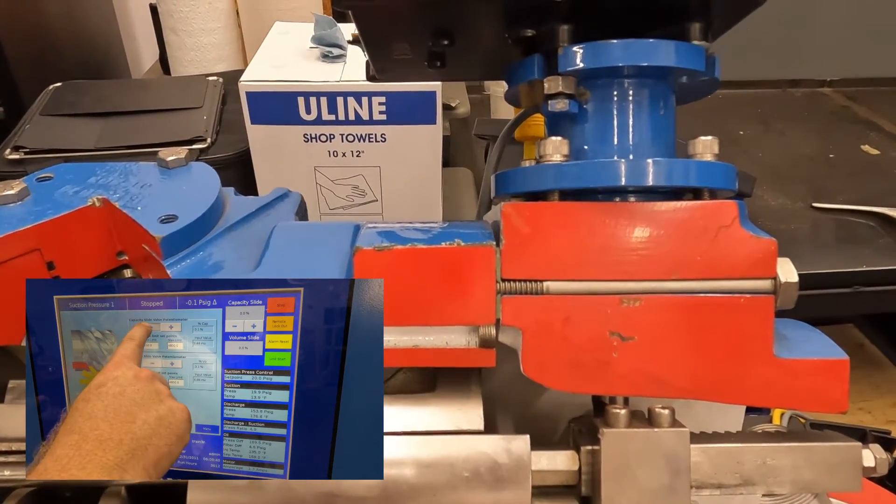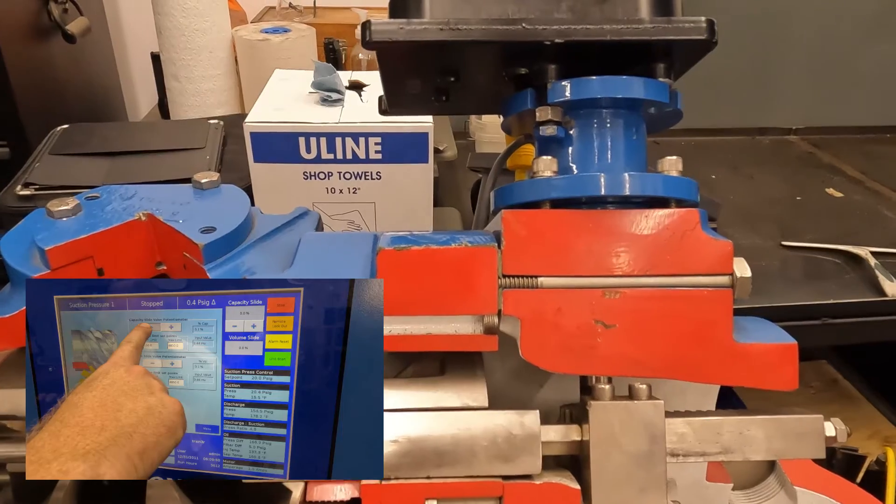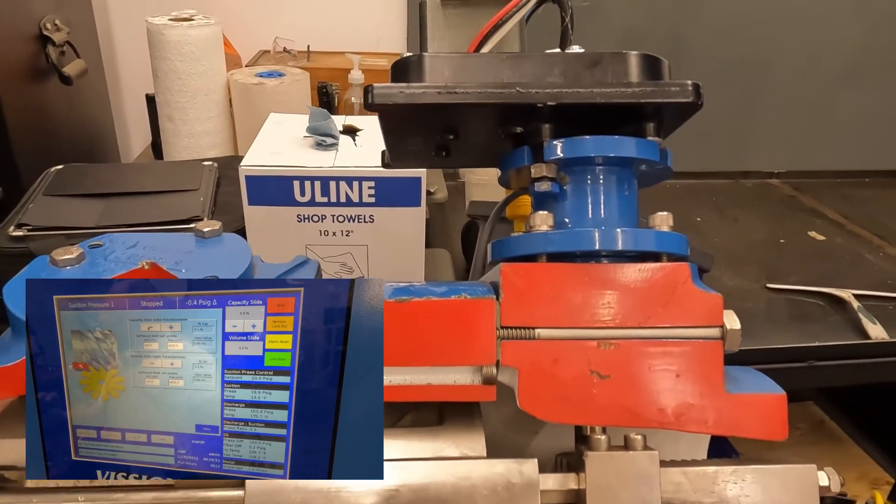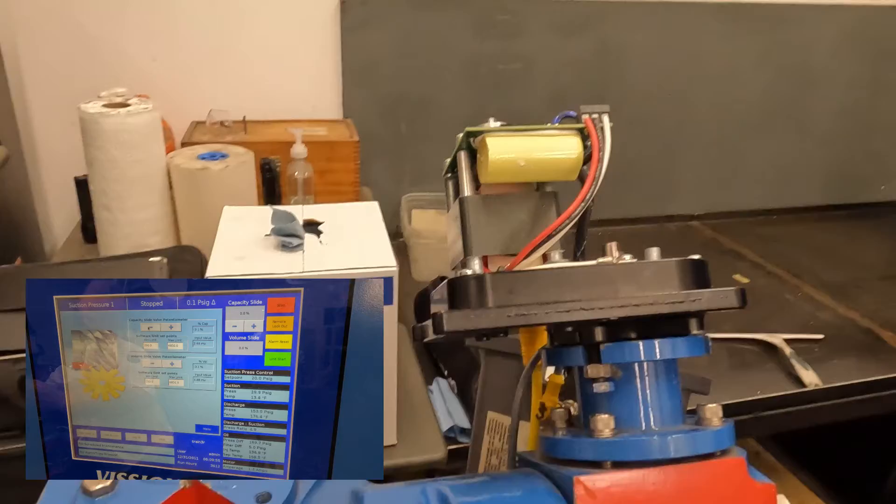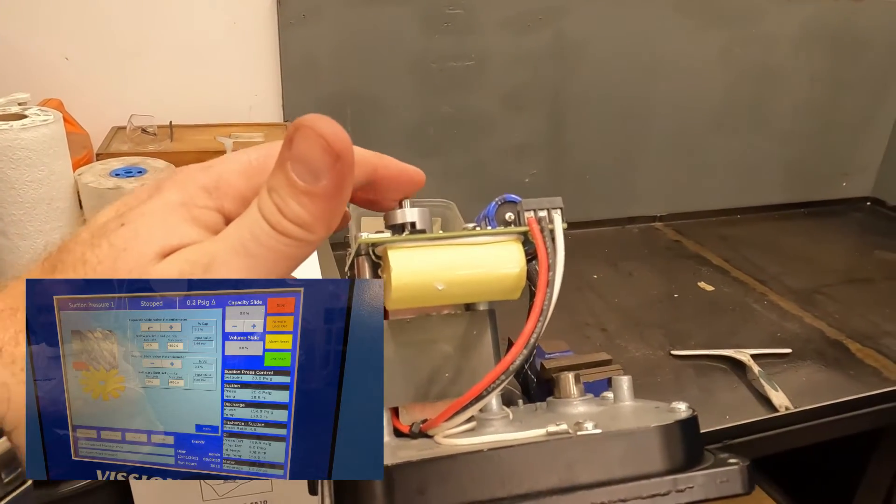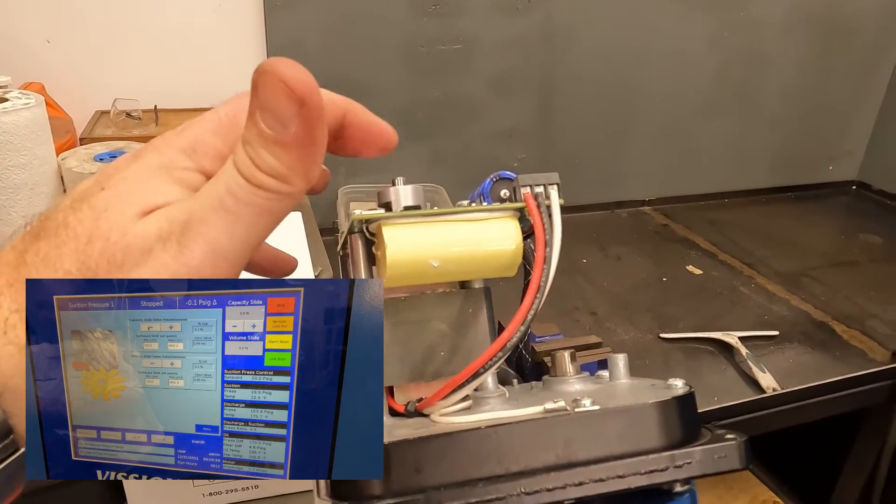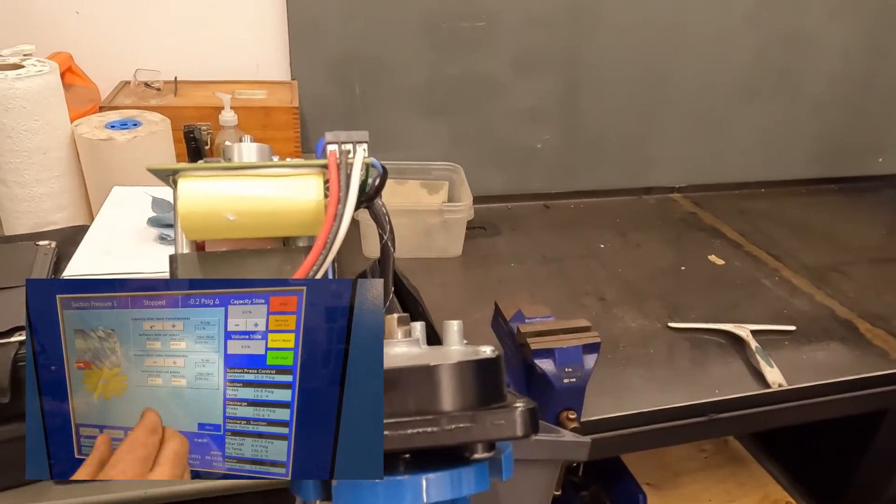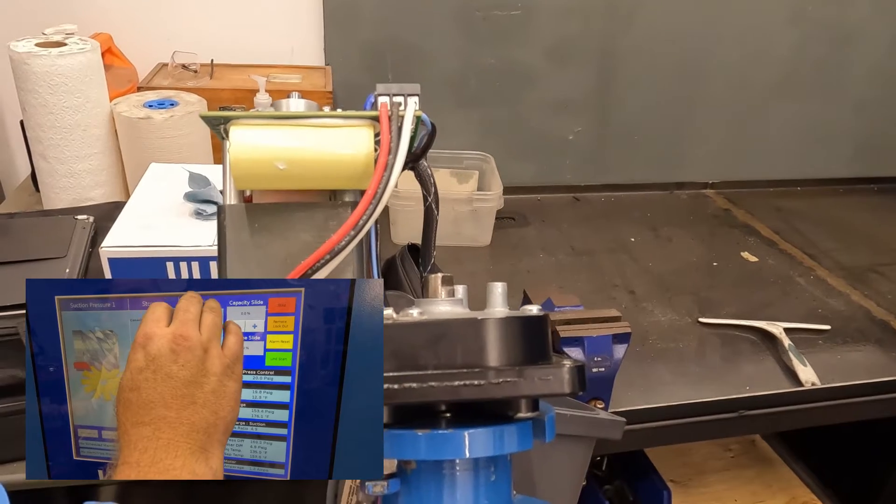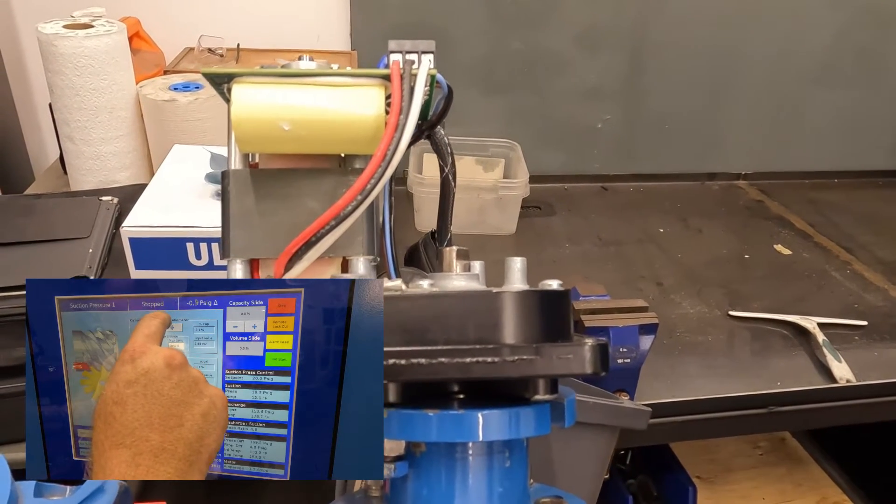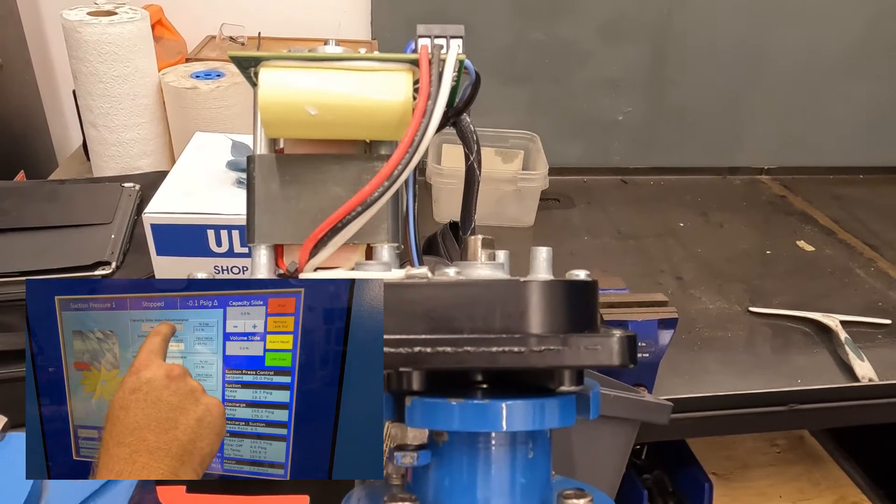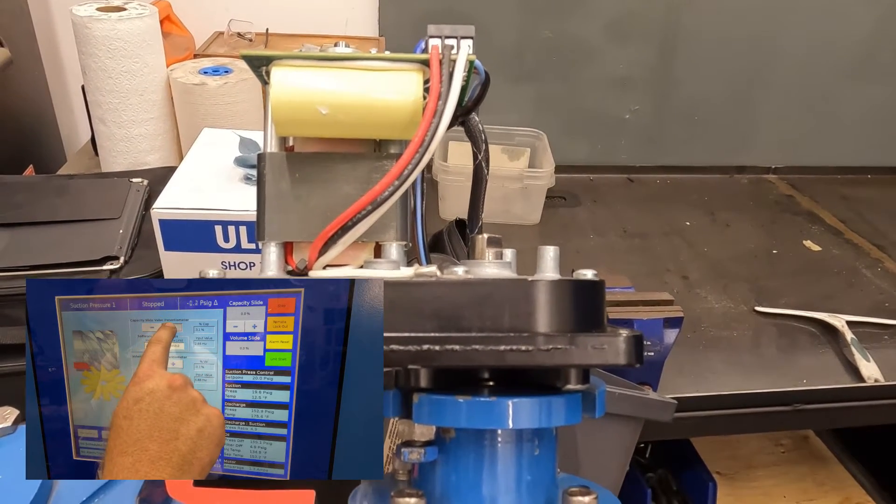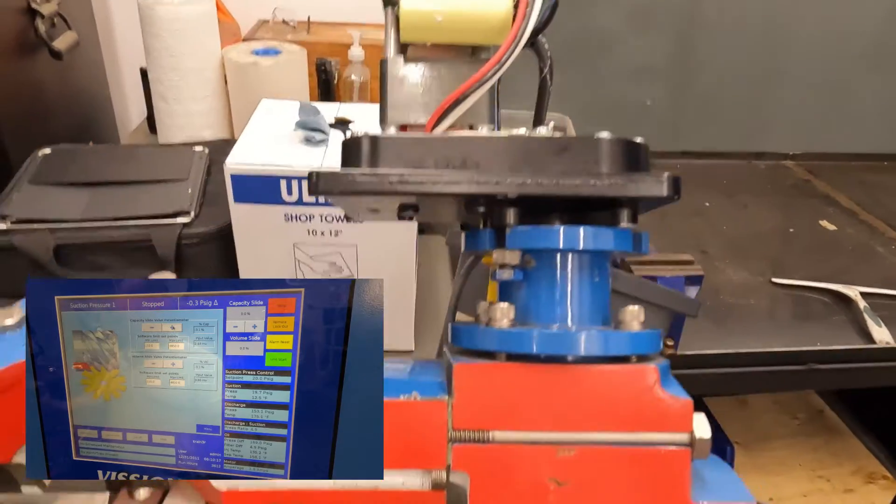So from here, we're going to finish going down to a minimum position. We're just going to keep going. You'll hear that motor load up. And that's how we know we're at the mechanical stop. So now that we're at the mechanical stop, we're going to release some of that tension off of the spindle, off the actuator. And we're going to increase. We're going to hit increase to move away from the mechanical stop. One, two, and that's away from our stop.